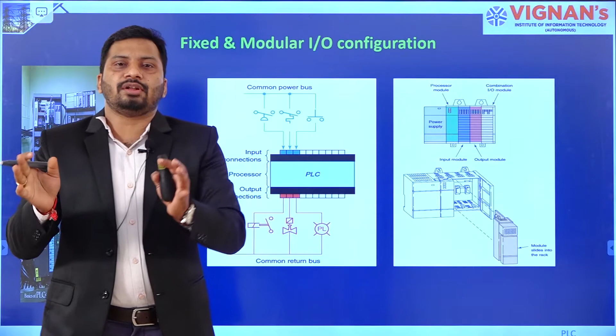So what is the drawback? You cannot go for a high-end modular type PLC for a simple process. A simple fixed PLC is enough for a small process. But if you want to control a slightly higher-end process, you need to go for the modular type. Another disadvantage is that if one module is damaged in the fixed one, you need to throw out the total device. But in a modular type, if the input module is damaged, you can replace the input module. If your output module is damaged, you can replace the output module. If you want to replace with a high-end processor, you can replace. That's what we already discussed.